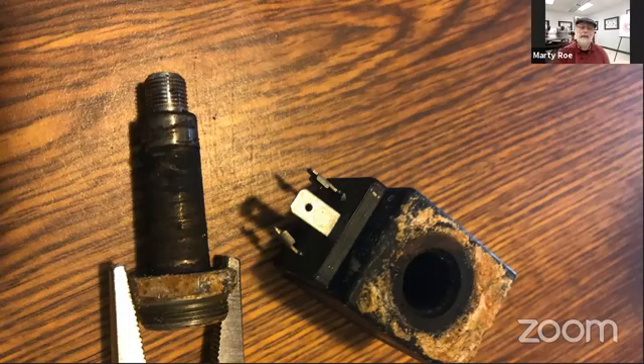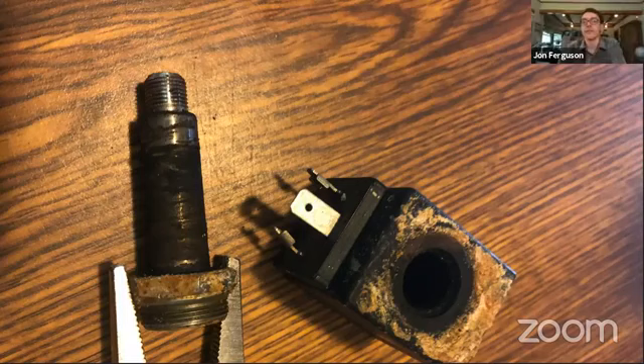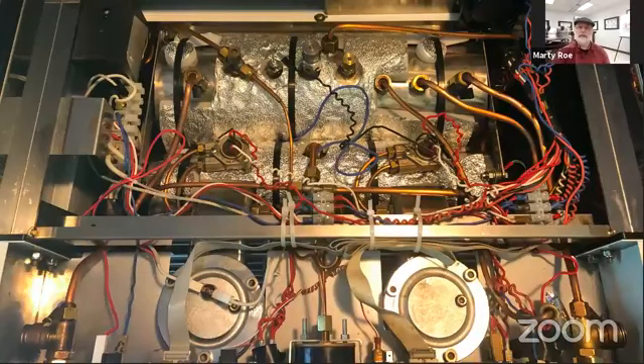So if you've got water that's extreme in alkalinity, pH, that sort of thing, it can be aggressive and can actually start pitting boilers, lines, and the metal within that stem. It has a plunger that slides up and down to open and close the valve, and there can be a wear spot in there, but more than likely it's either a manufacturing defect or the water has been a little too aggressive.